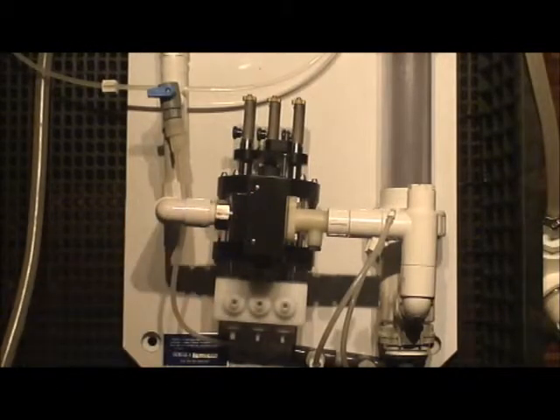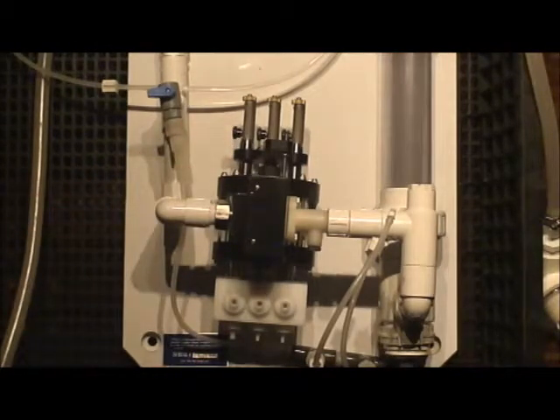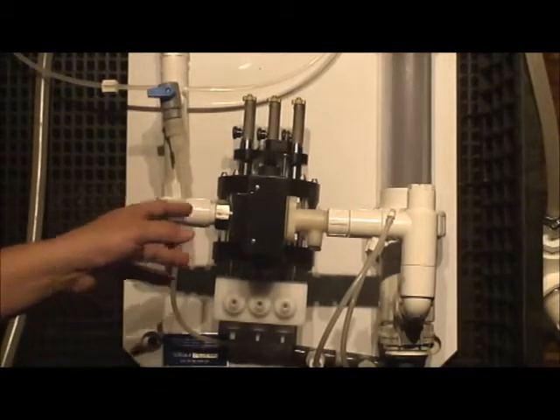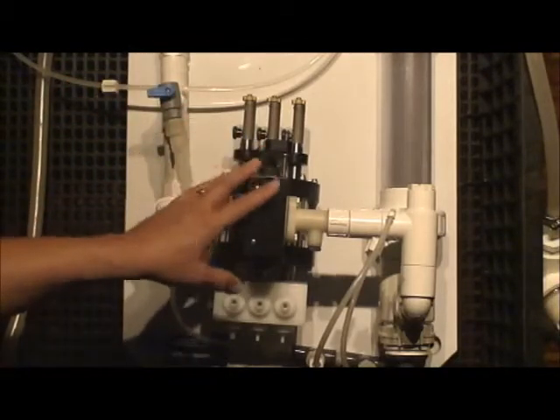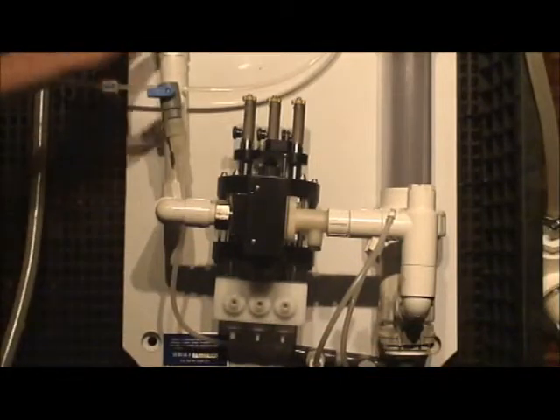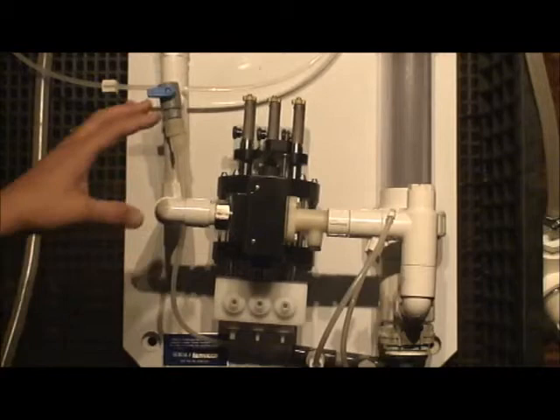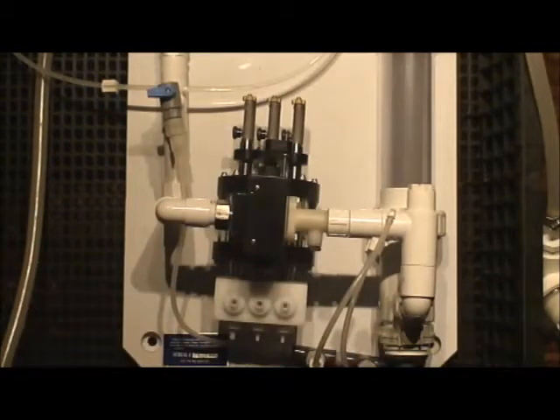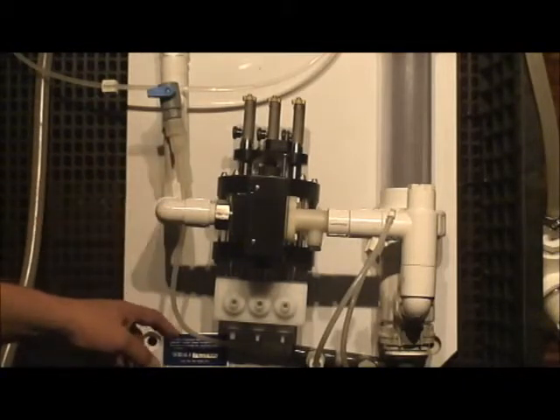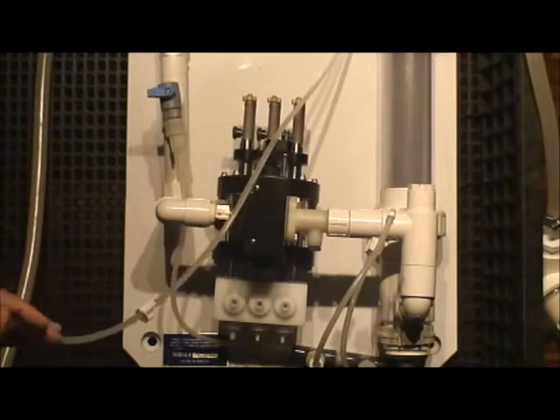As you look at this, you start to notice that once again we have this tubing here. And you might recall that what I said is that this tubing is connected to the far left of your pump, down here in the base. So if you watch, I'm taking that tubing with those two little fittings there that prevents leaking from occurring. I'm going to slide it in, then I'm going to bring in this little nut and screw it in, and that is exactly how you connect the tubing for your total.